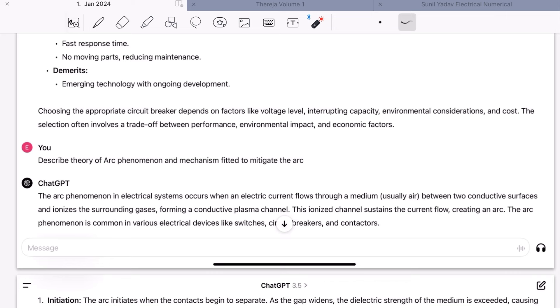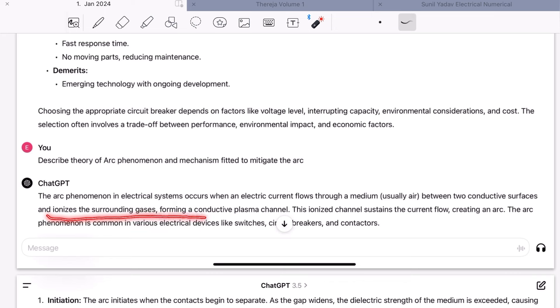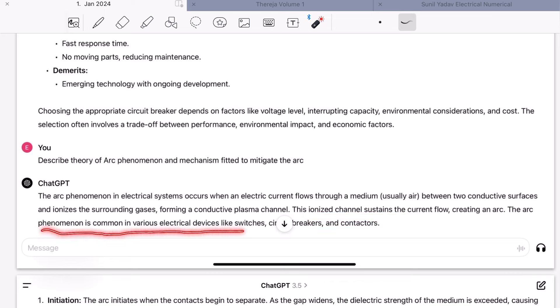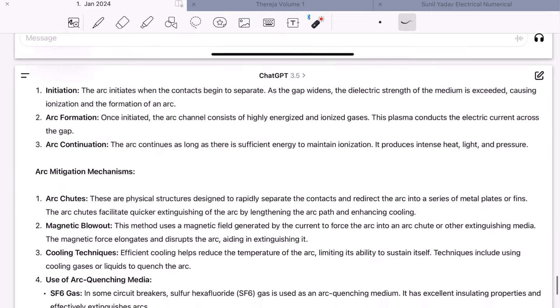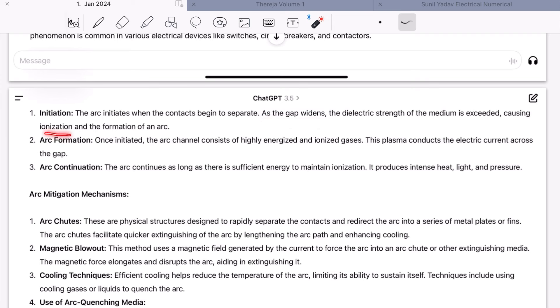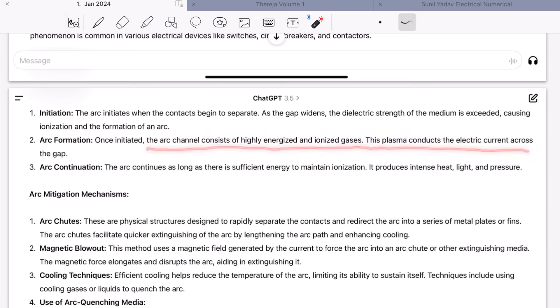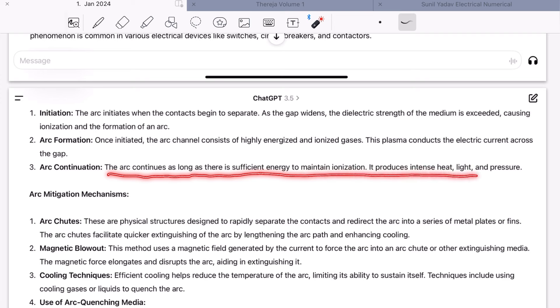You should know what arc is and how it is created. Arc phenomena in an electrical system occurs when an electric current flows through a medium — usually between two conductor surfaces — ionizing the surrounding gases and forming a conductive plasma channel. This ionized channel sustains the current flow, creating an arc. The arc is common in devices like switches, circuit breakers, and contactors. The arc initiates when the contacts begin to separate. As the gap widens, the dielectric strength of the medium is exceeded, causing ionization and formation of an arc. Once initiated, the arc channel consists of highly energized and ionized gases, which conducts electric current across the gap. The arc continues as long as there is sufficient energy to maintain ionization, producing intense heat, light, and pressure.